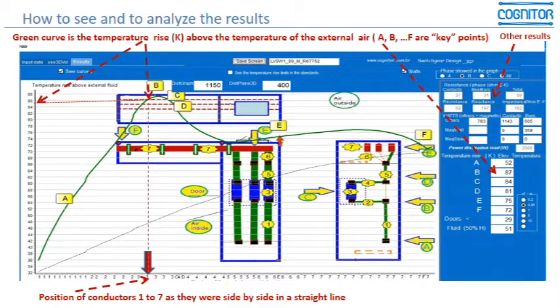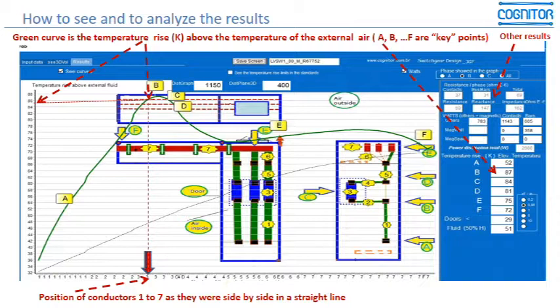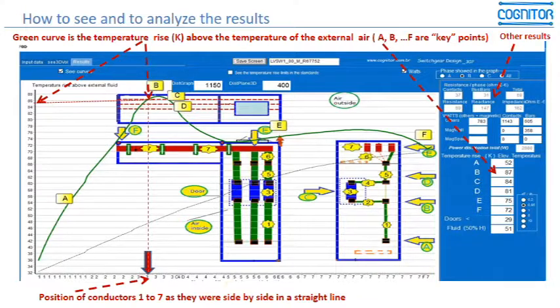Take a look at the horizontal axis at the lower part — these are the conductors one to seven as they appear side by side. The value of temperature rise appears on the left-hand axis. On the right side of the figure you see points A, B, C, D, E, and F — these are doors and fluids measured at 50% of the height of the compartment. These are the temperatures measured at those points, which correspond to the measurement points specified in IEC standards for temperature rise tests done in a laboratory.